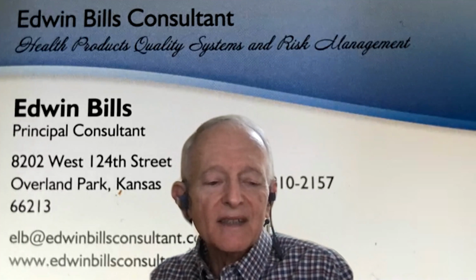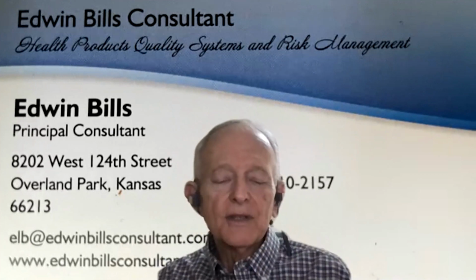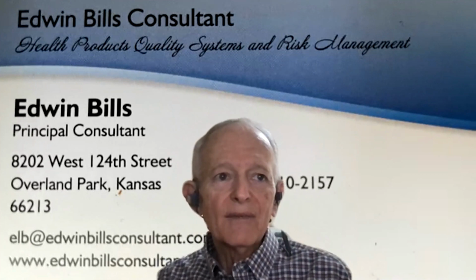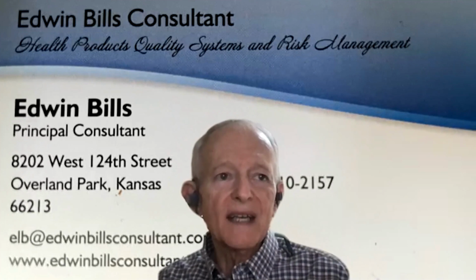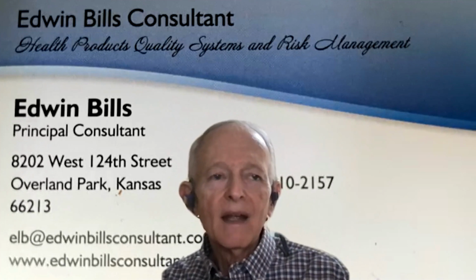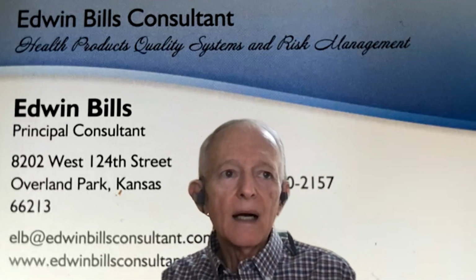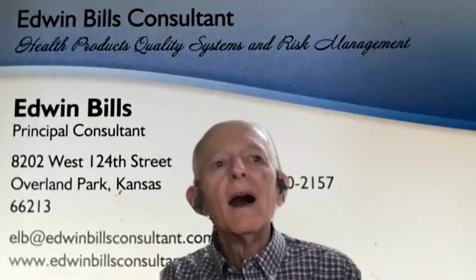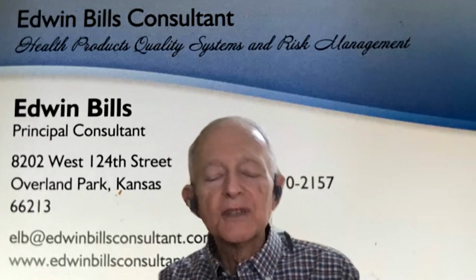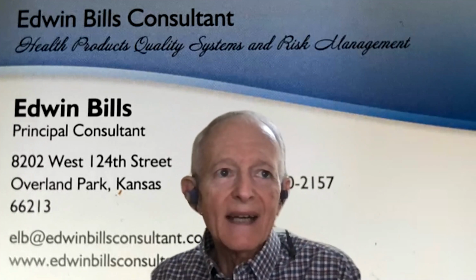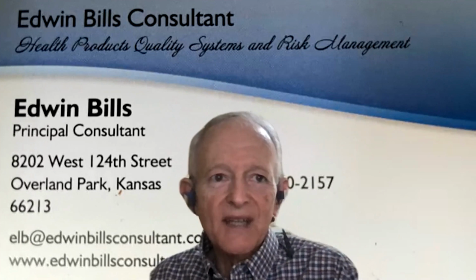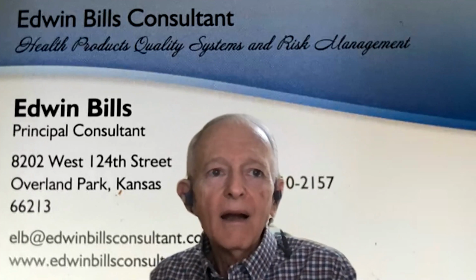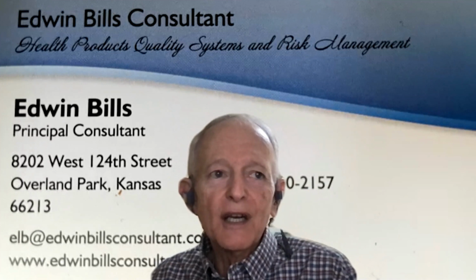And part of the requirements in the standard are that you do individual benefit risk only for those things that are not acceptable. And then you would use that to determine how much risk control you need to add to reduce that risk down to an acceptable level, or decide if it's good enough.